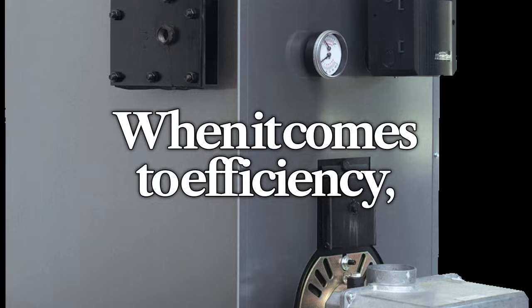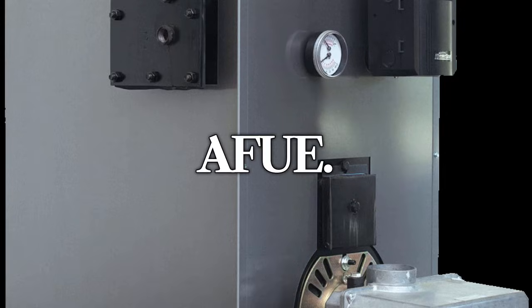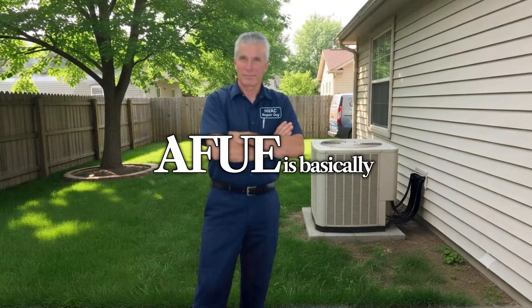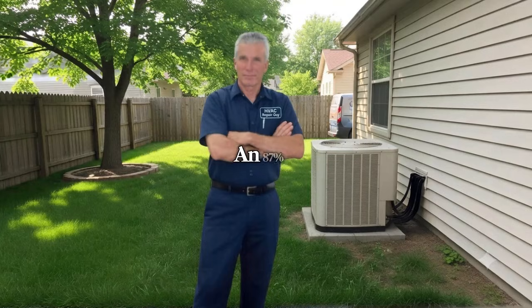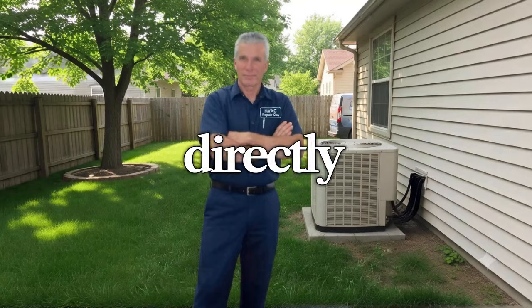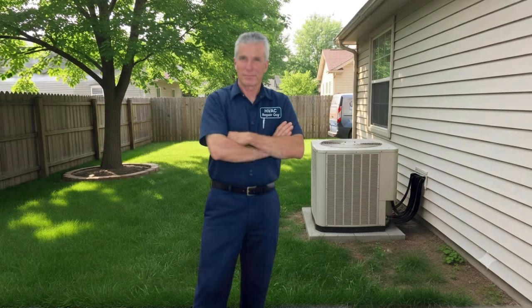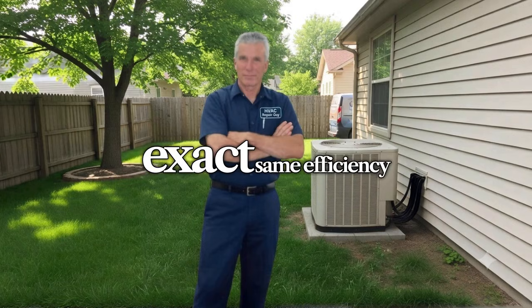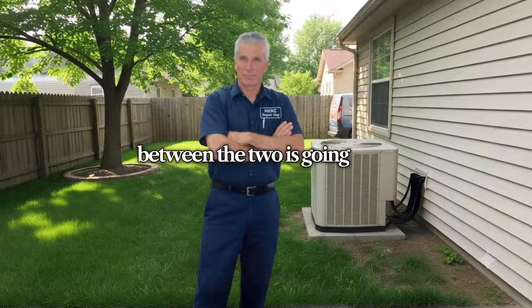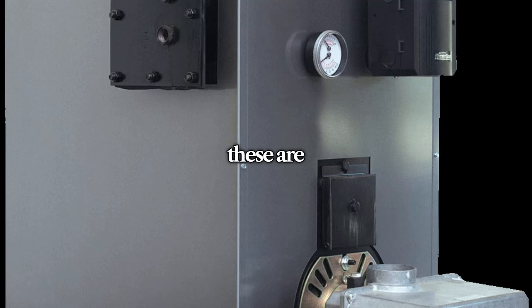When it comes to efficiency, both boilers are rated at 87% AFUE. AFUE is basically your boiler's fuel efficiency rating. An 87% rating means that 87 cents of every dollar you spend on heating oil goes directly into warming your house, while the remaining 13 cents goes out the vent. Since both units hit the exact same efficiency mark, fuel consumption between the two is going to be virtually identical. Neither of these are condensing models, so you won't have to worry about complex venting setups or extra condensate drainage lines, which keeps the mechanical setup standard and straightforward for annual maintenance.